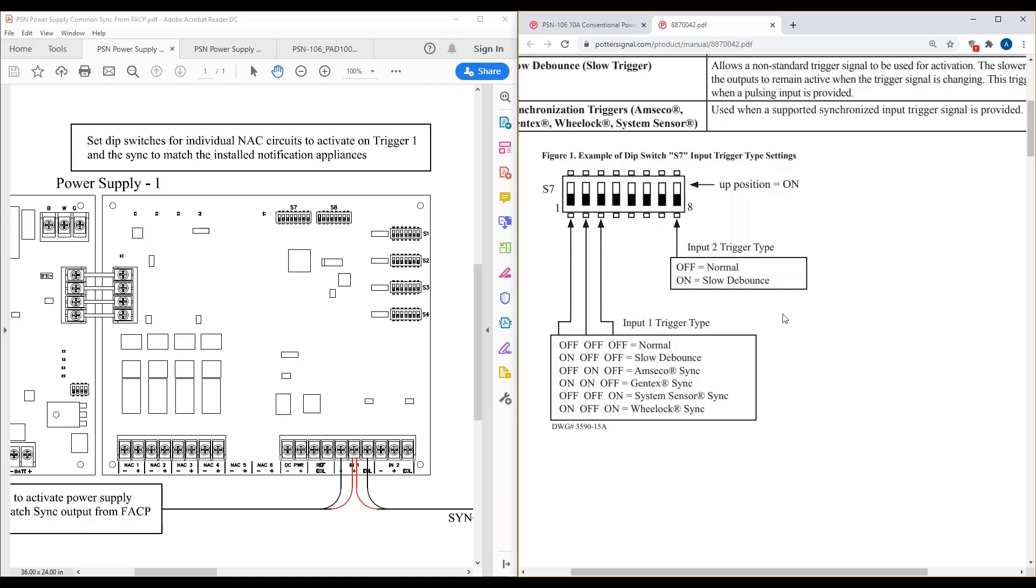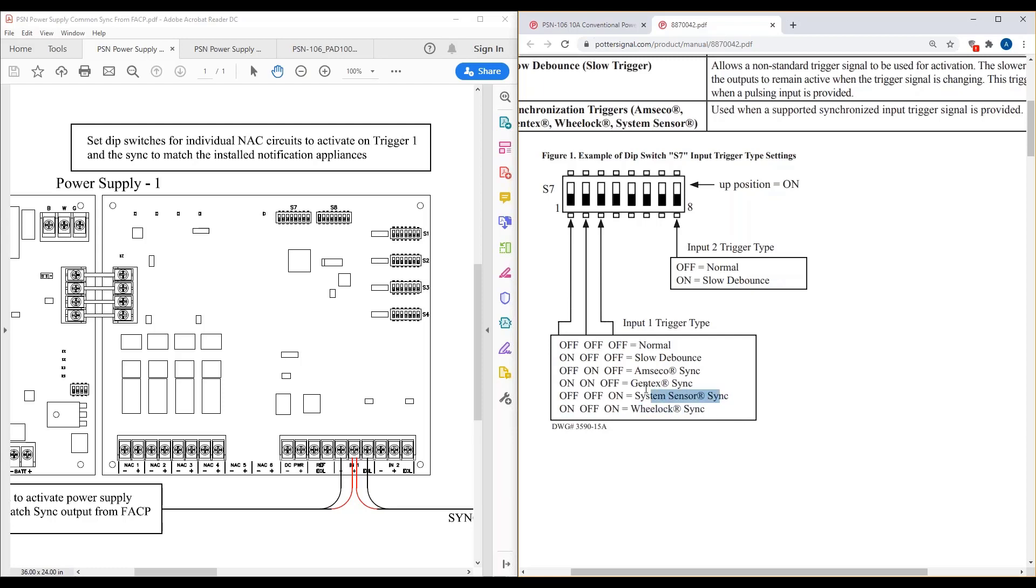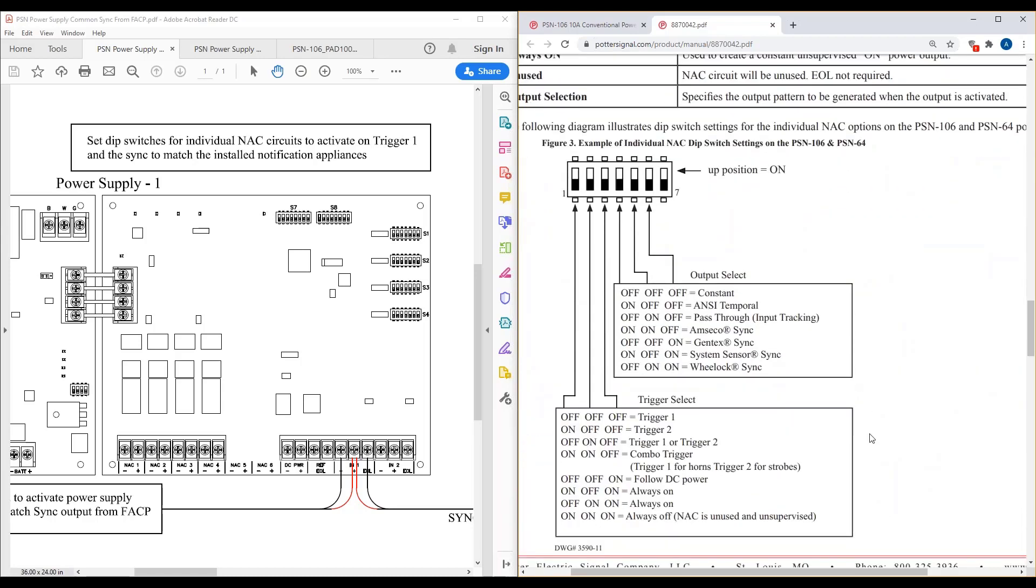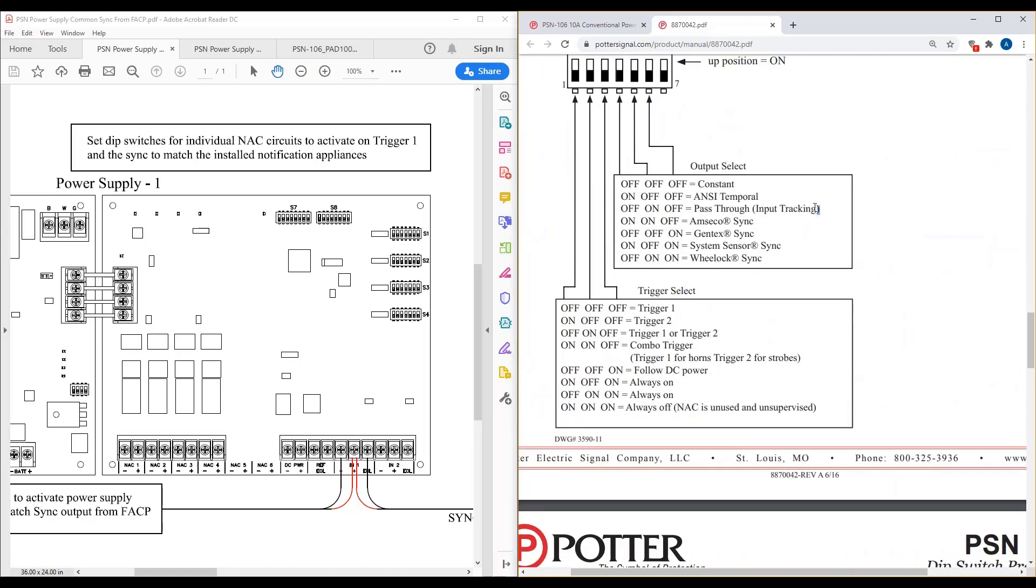If you look at this, this actually defines the incoming synchronization. And this is where people get confused sometimes. So if you know you have a system sensor sync triggering the power supply, you're going to set dip switch bank S7 up as a system sensor sync. If you know it's a Gentex sync, you can set that up as on, on, off. So this is telling you what your incoming sync is. If you're using something other than one of these sync protocols, you can always set it up as normal. What normal is, it's basically like a pass-through. So it's going to take whatever that sync generator was, you know, maybe it's a simplex panel. It will take that simplex sync and just redistribute it to these individual NAC circuits.